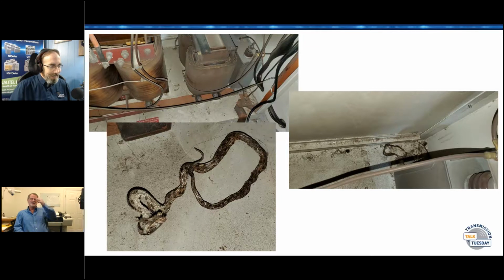This is a Harris high voltage power supply for a Harris HT25. I got a call one day that the 80 amp breaker at the front wall tripped on this thing. Well, it just never happens.